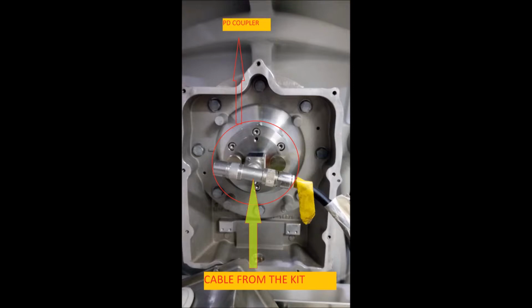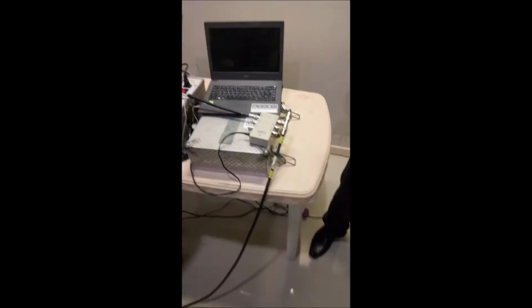As a result, original equipment manufacturers provide a provision for measuring the partial discharge through PD couplers which are provided all across the GIS. These boxes are placed in such a manner that they can cover all the GIS equipment such as bus bars, cable chambers, isolators, earth switch, etc. To be precise, the total area of GIS has to be covered.